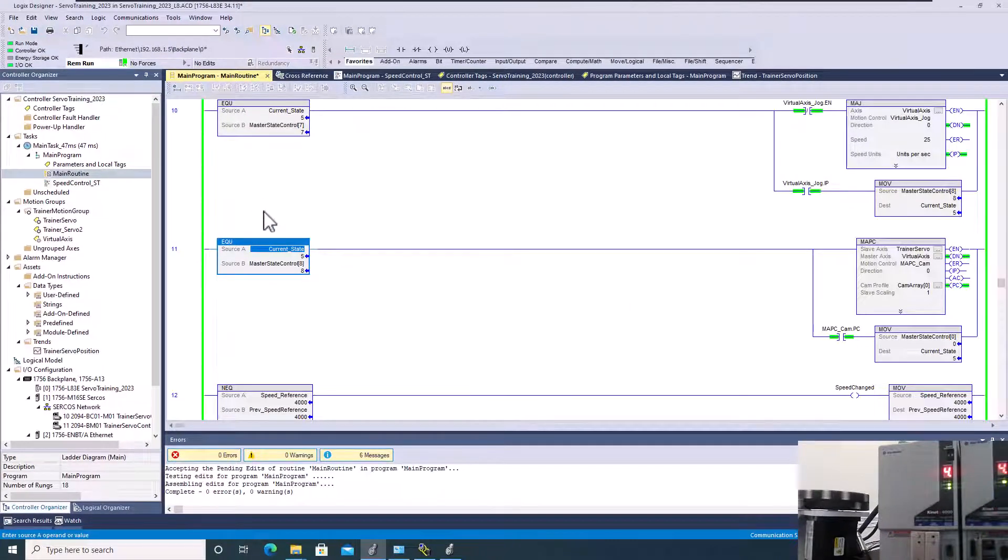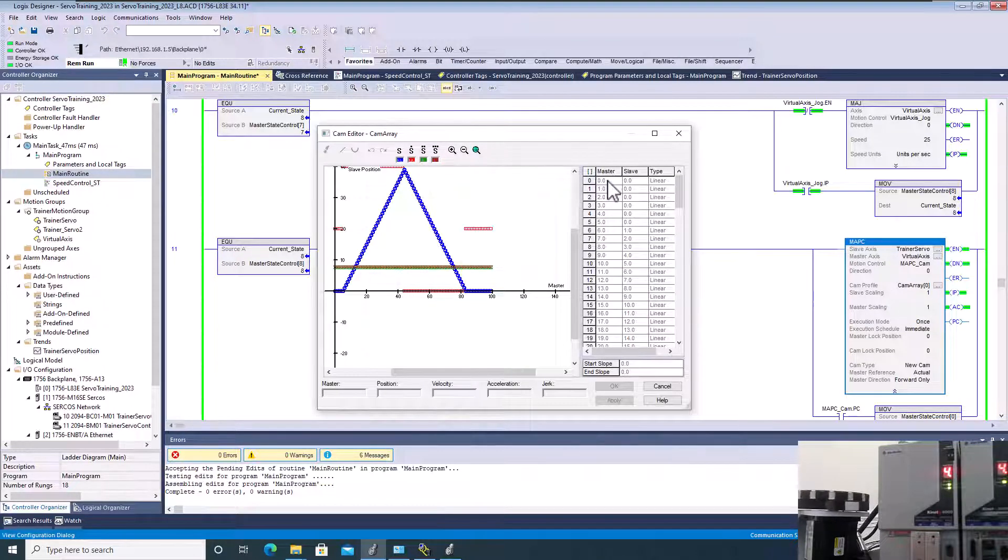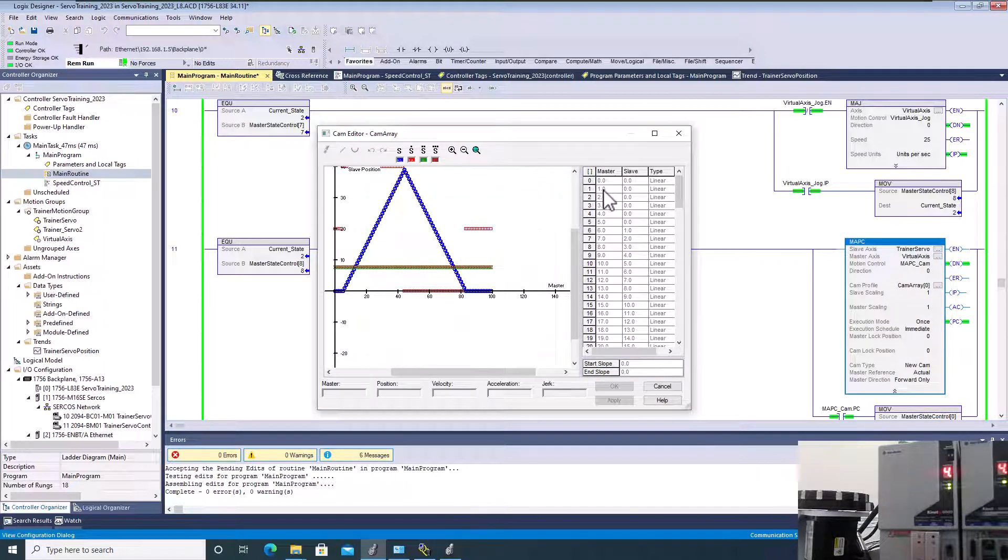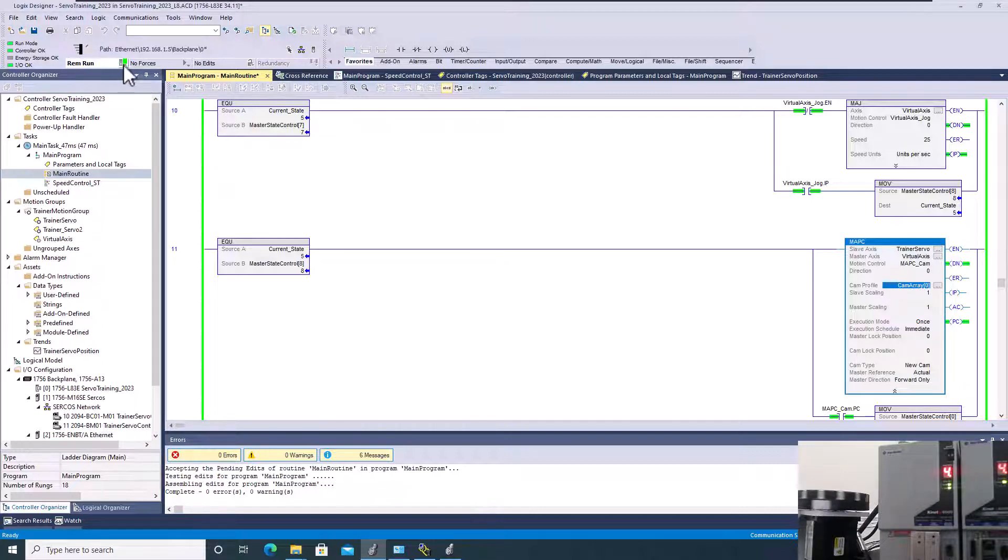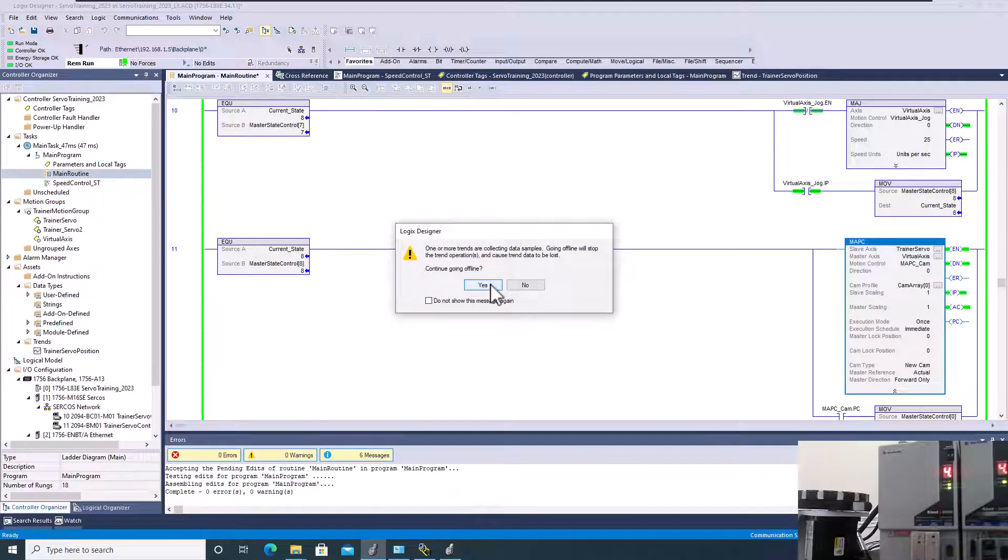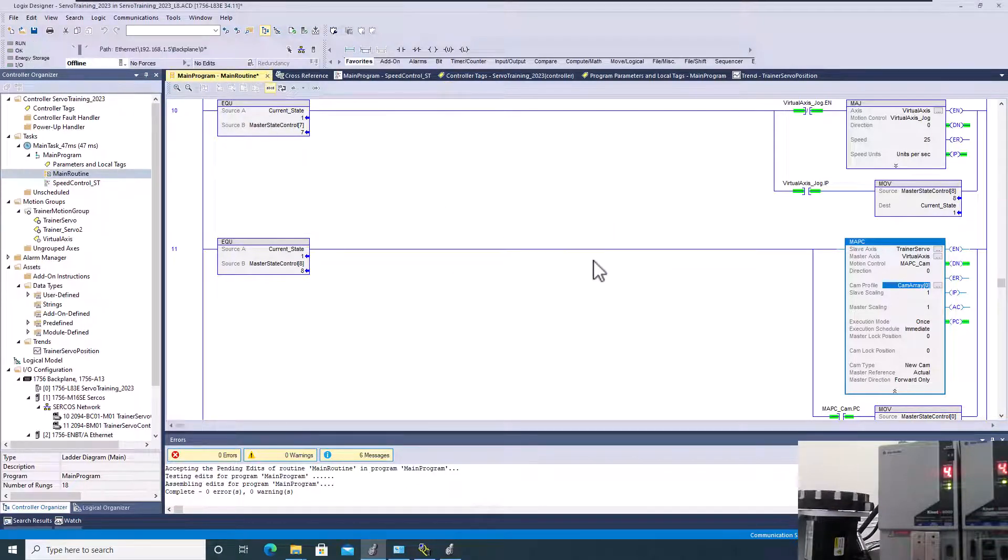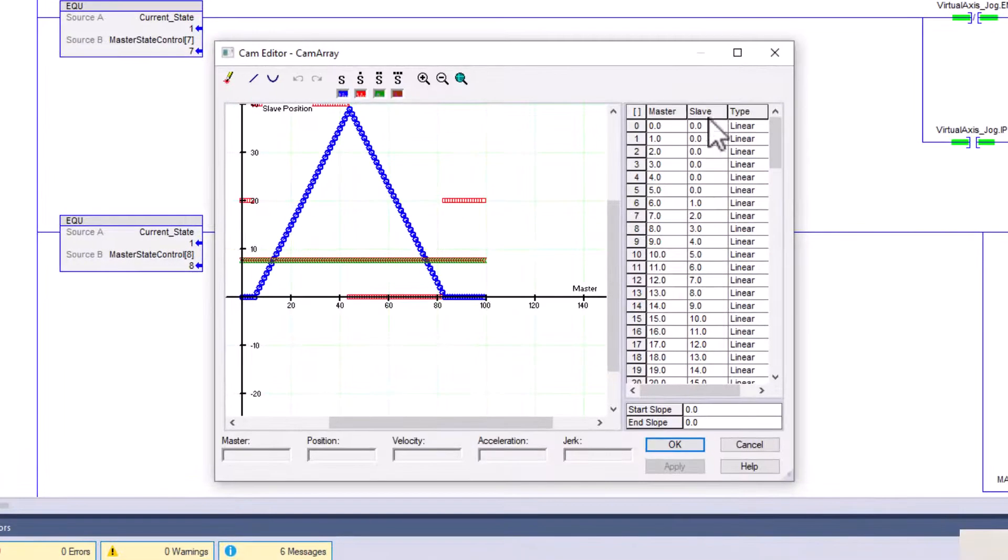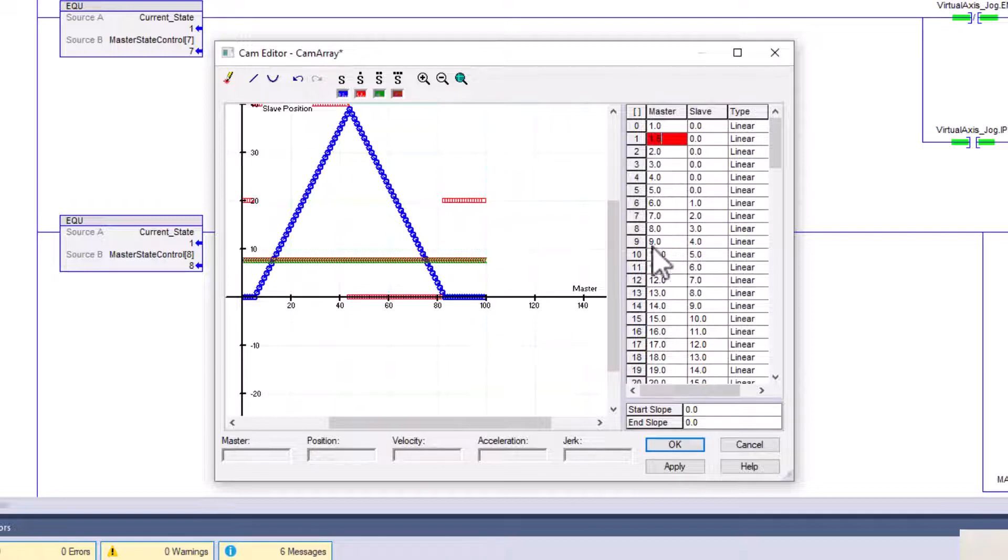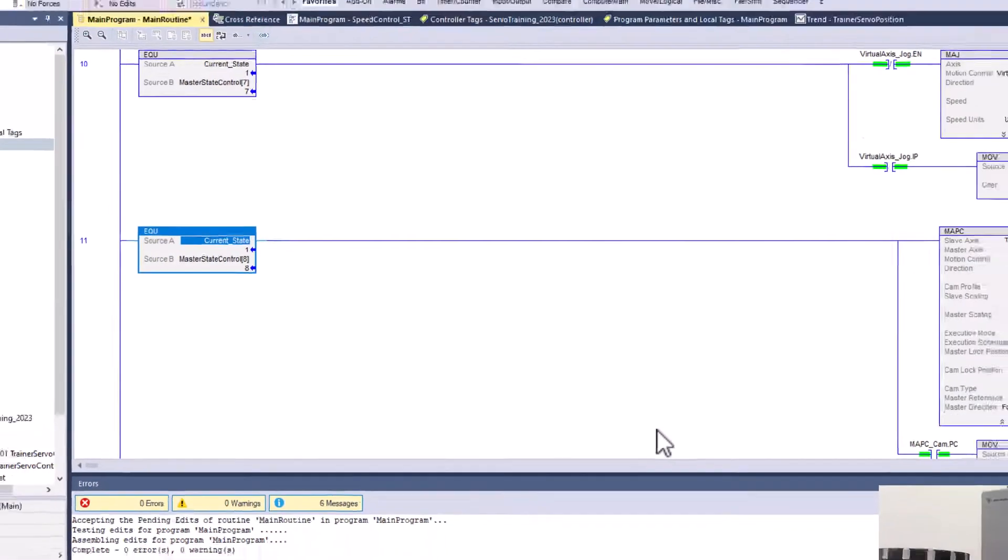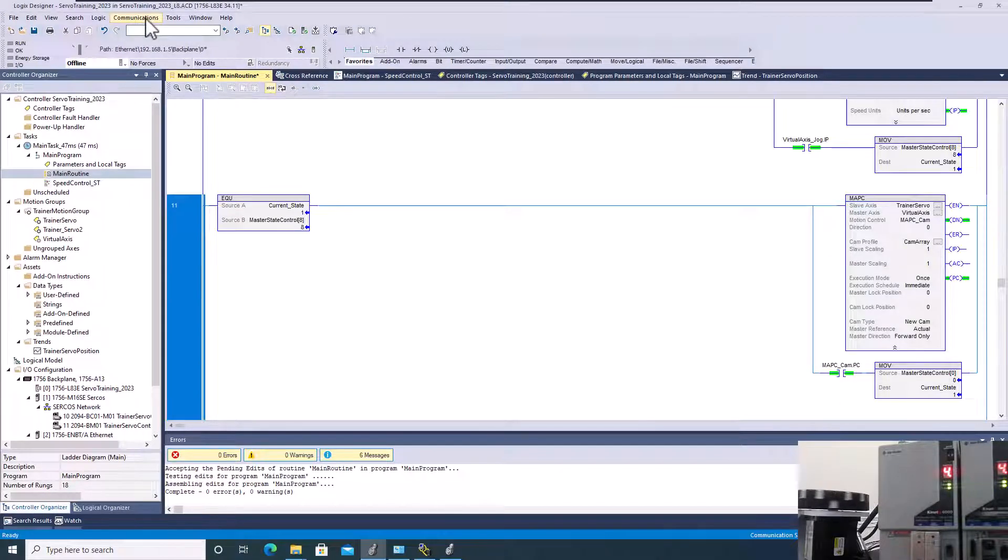Now the exact error that I had was because I was not starting my actual master at zero. I was locking my cam of my master at one. And then to make that matter even worse, I didn't have the first array. So I could go offline and download to this and show you this real quick. So I actually do have some trend running, but what we'll do is we'll change this. We'll change this to what this was, and we'll have this start at one. And we have to actually change that a little bit. So let's go in here and do exactly how I derived my error before.